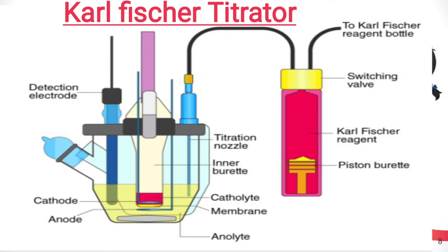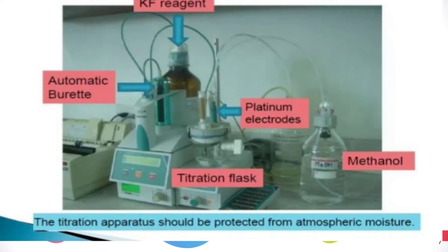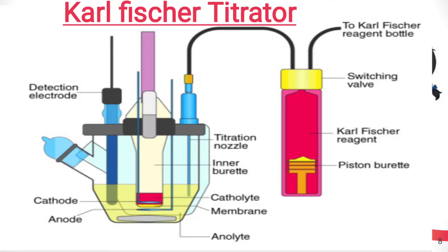Here is one more diagram of the titrator. On the top we can see the detection electrode, cathode, anode, anolyte, catholyte membrane, inner burette, titration nozzle, and piston burette. The basic ingredients of Karl Fischer reagent are filled inside this burette.